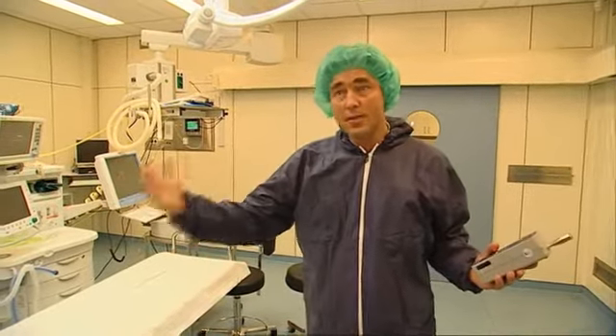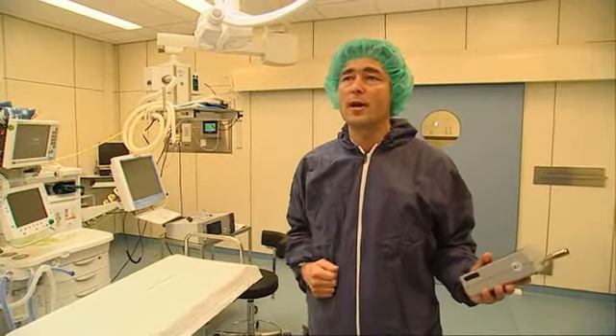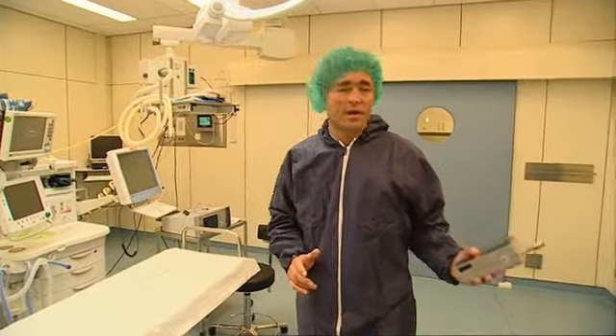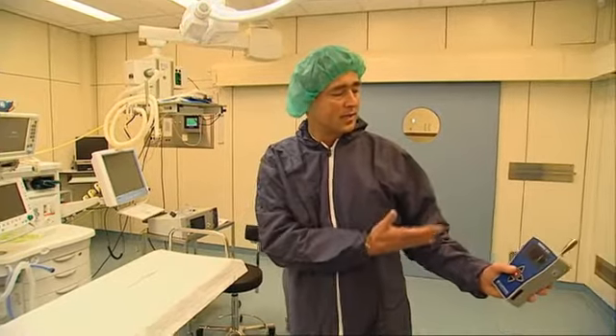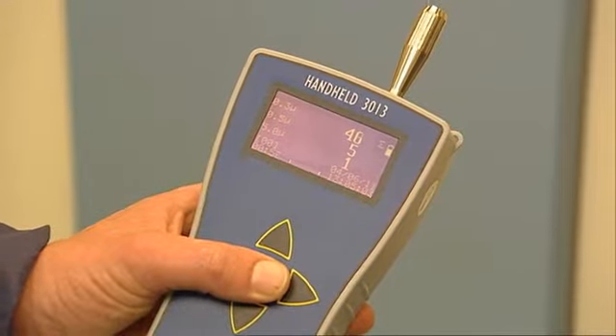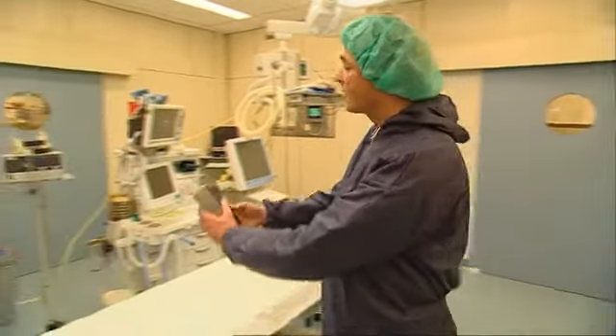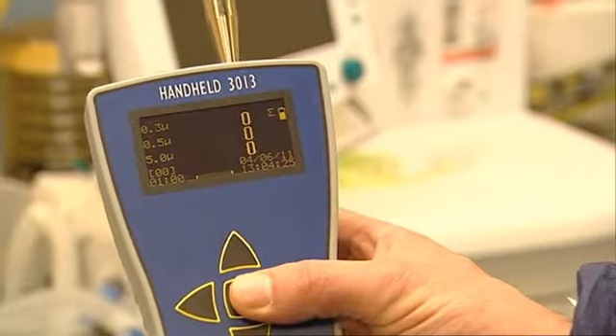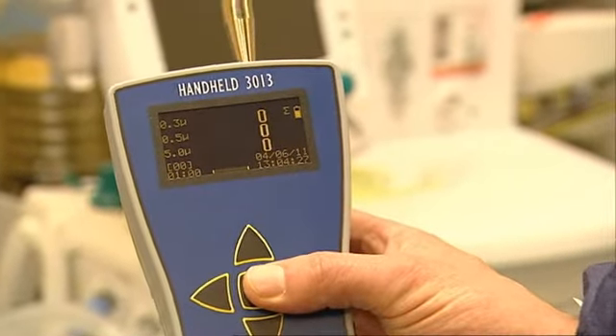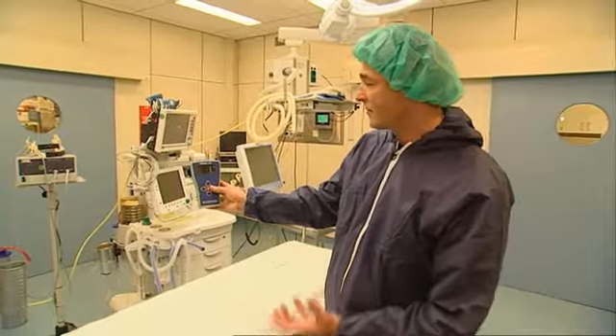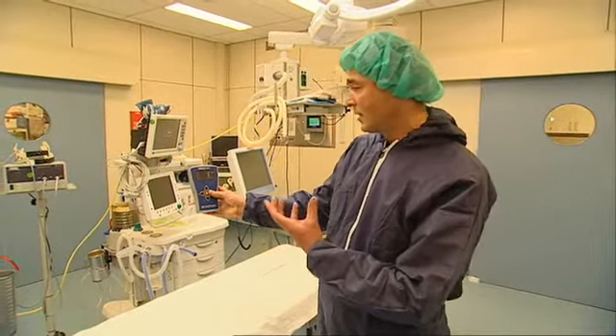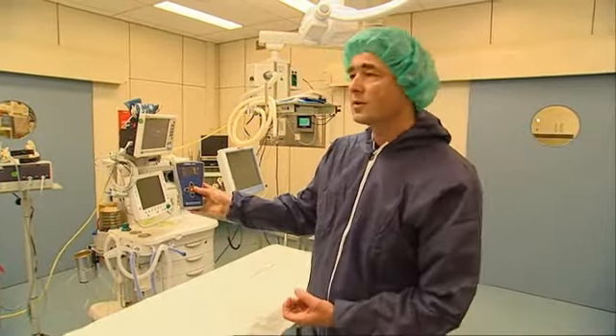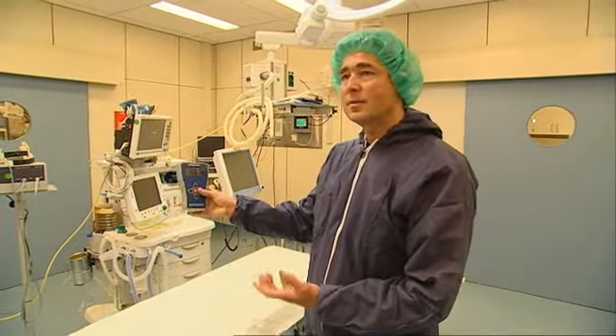We are here in an OR, where the air has to be clean. Clean air should be free of particles that may carry bacteria, so we want to reduce the amount of particles. If I activate this particle counter, you'll see the amount of dust particles here. If I measure it again under this downflow plenum, you'll see that clean air is provided on the patient bed. That's the core of Lighthouse's monitoring system. It monitors and controls the parameters needed to keep the patient clean.